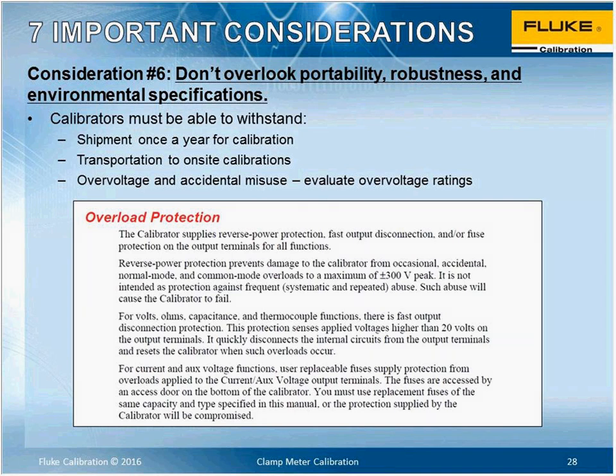So when you look at portable calibration products on the market, they don't always get to the accuracy that many would need to take on-site and calibrate 3.5, 4.5, 5.5 digit DMMs. What's important to look at: what safety is built into it, how robust is it, and has it got the right casing to accept and transport it?